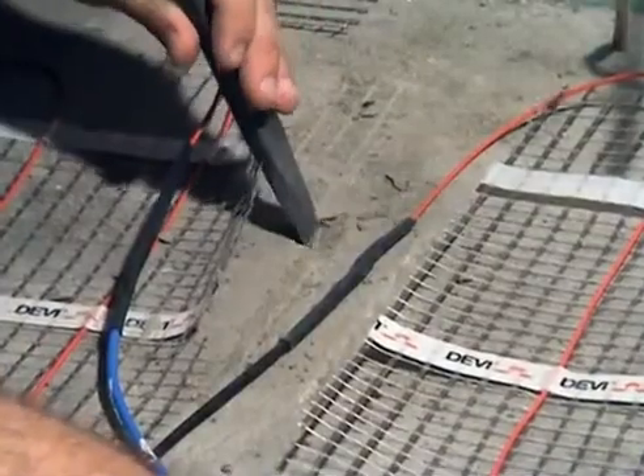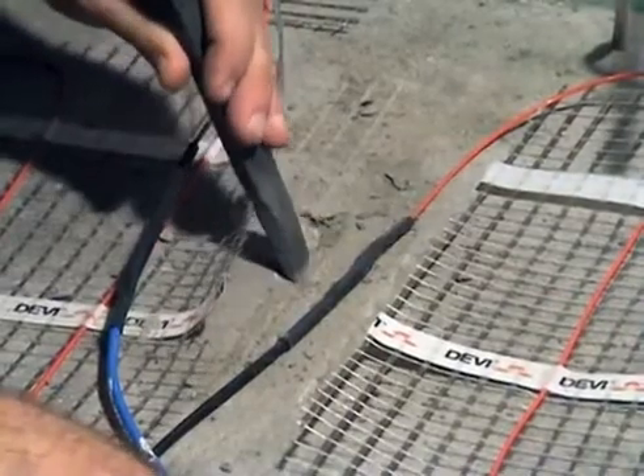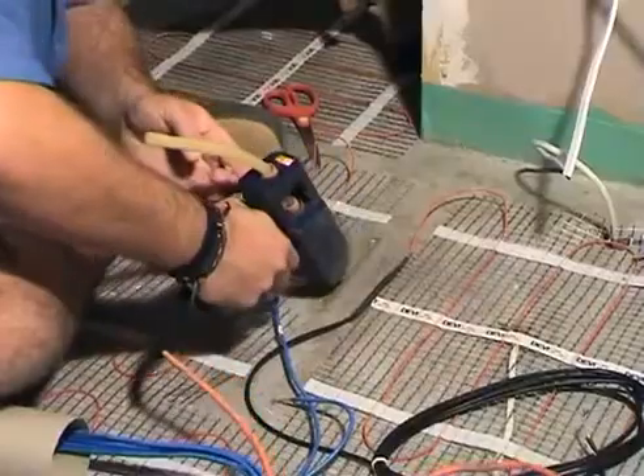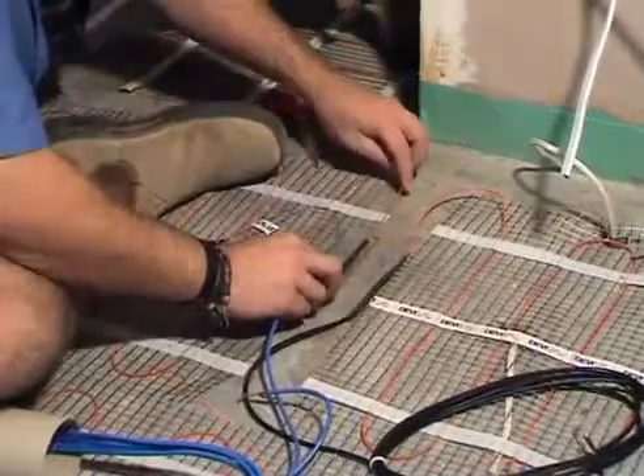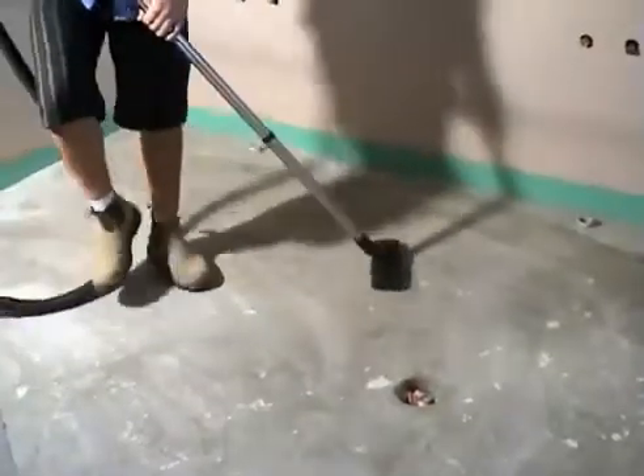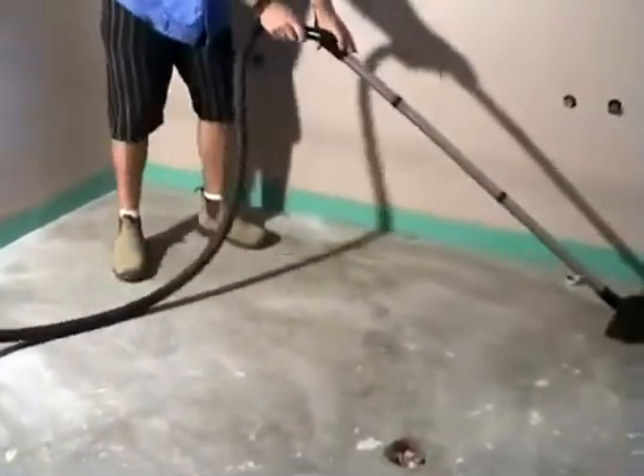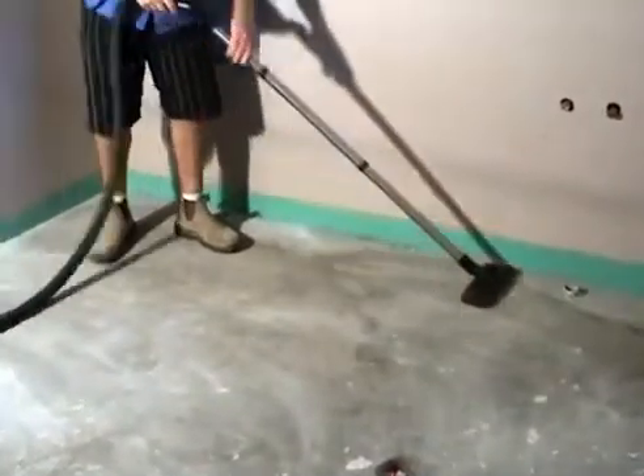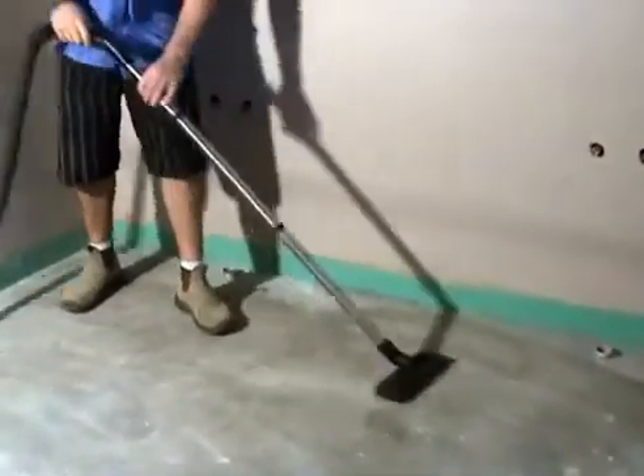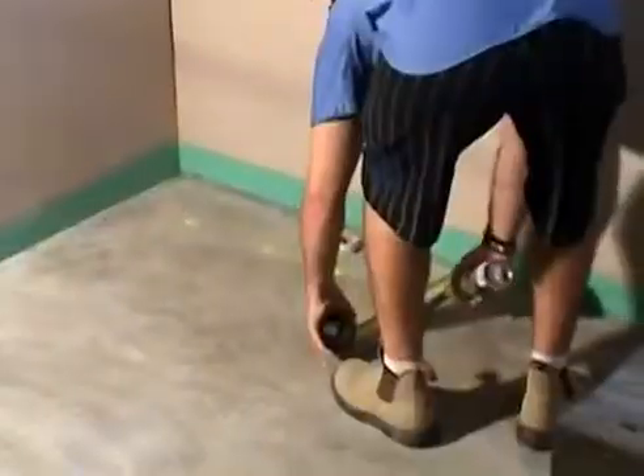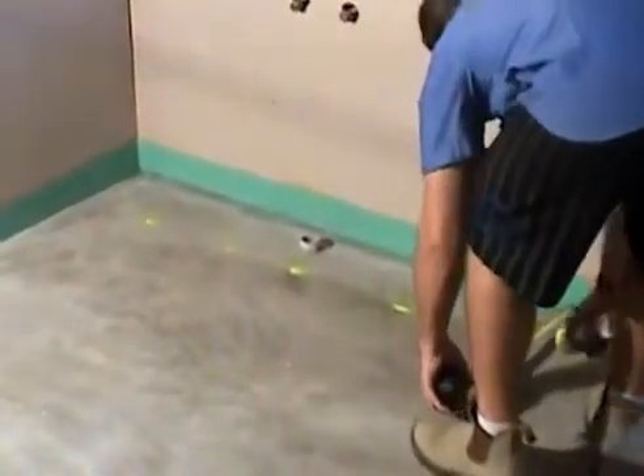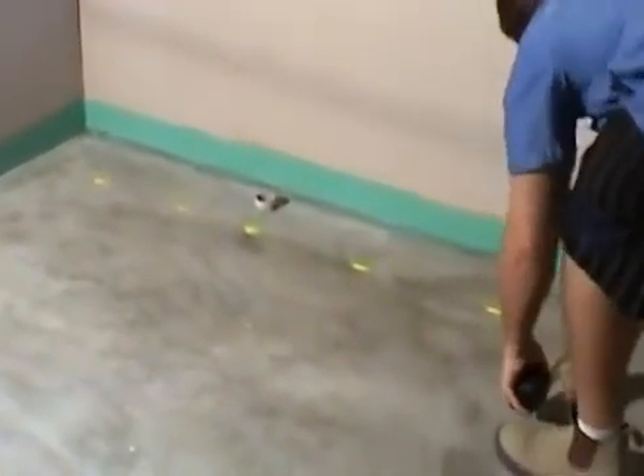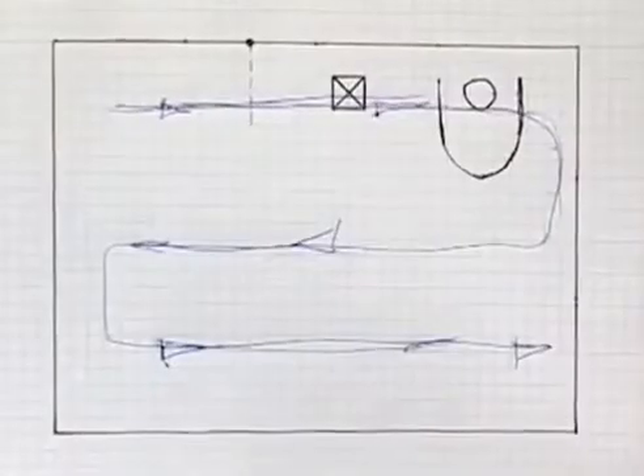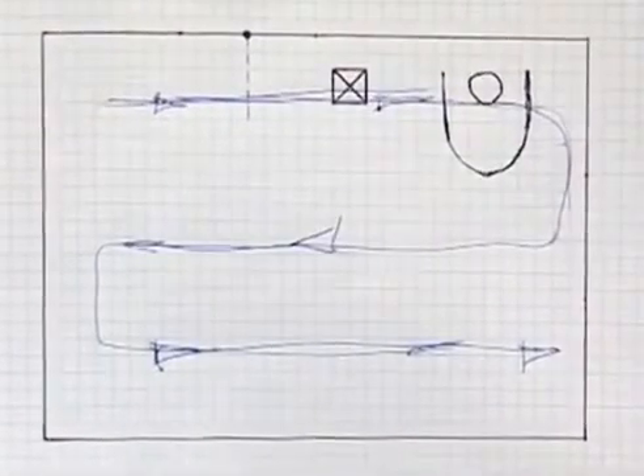Both conduits will need to be chased into the subfloor structure, as the Devimat system is only covered by 10mm of glue adhesive. You are now ready to install your floor heating system. Make sure that the floor is clean and clear from all dust and debris. Mark out the positions of any permanent fixtures. Use your sketch to plan where you will lay the mat.